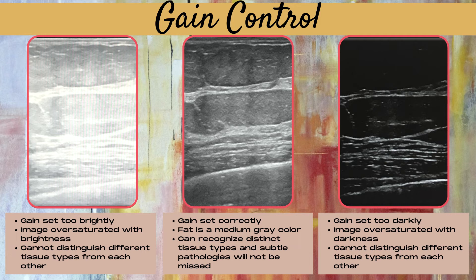Now let's do a little test I like to do with my ultrasound students. How do you know if your gain is too bright or too dark? Your gain is too bright if you need sunglasses to look at your image. Your gain is too dark if you can't distinguish each separate tissue type on the image, such as different organs or fat versus muscle. This is a quick test to tell if your gain is at the correct setting.